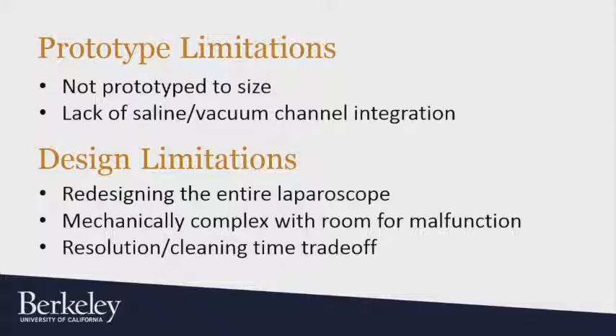And so our prototype has some limitations. The first one being it's scaled up 10 times from the actual proposed device, and we had a lack of saline and vacuum channel integration. Beyond that, our design has some limitations itself. We can't just simply put an add-on to the end of a laparoscope because you have to integrate the lens inside this glass sphere. So you would have to create an entire modified laparoscope. It's mechanically complex, which provides room for malfunction, and there's a clear trade-off between image resolution and cleaning time.